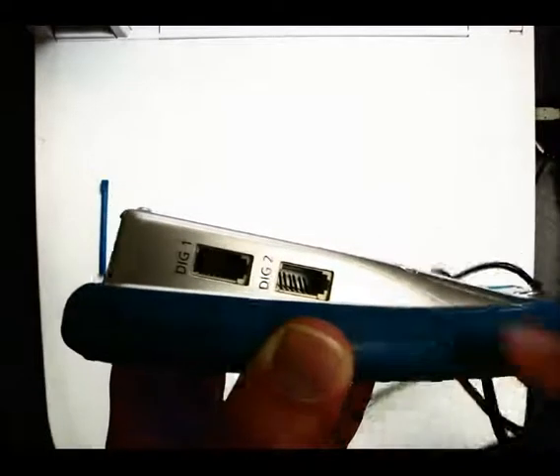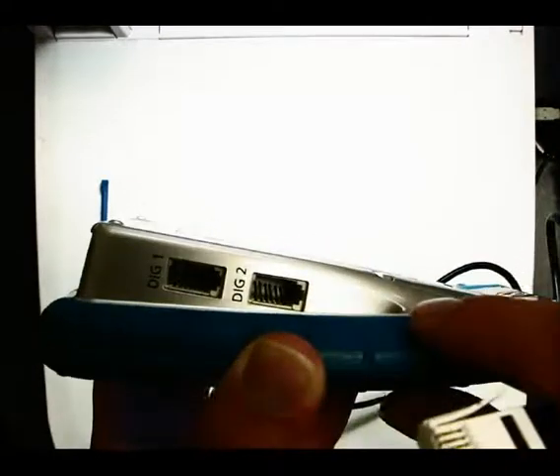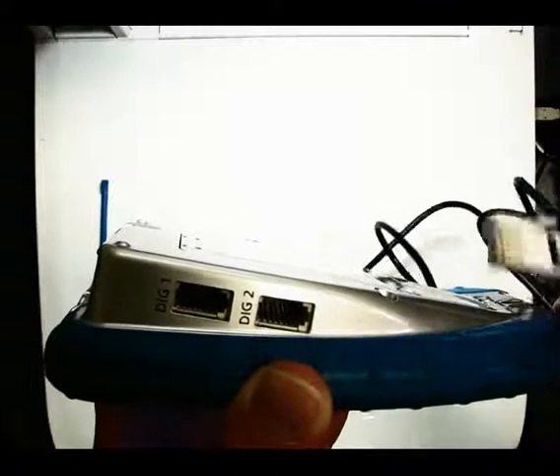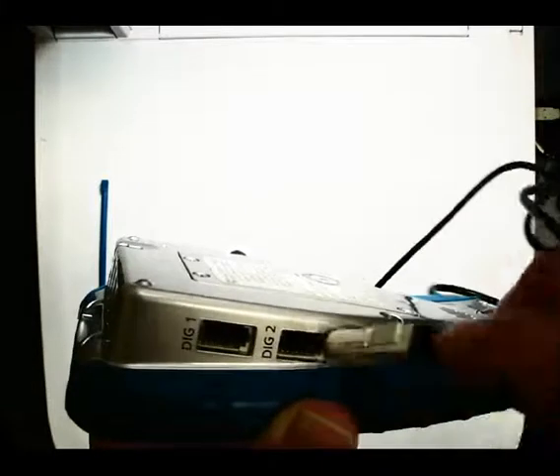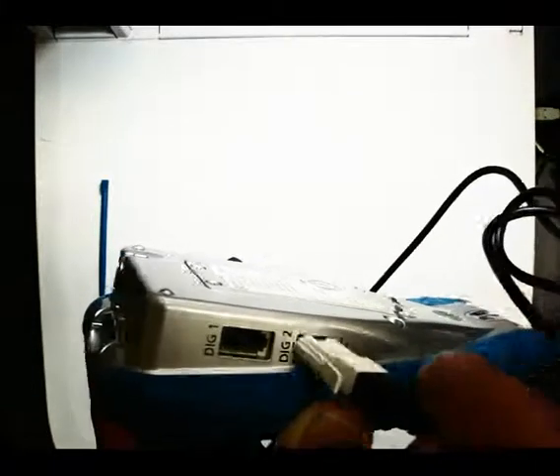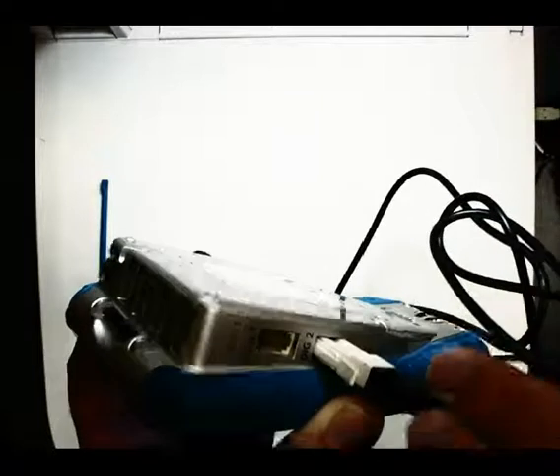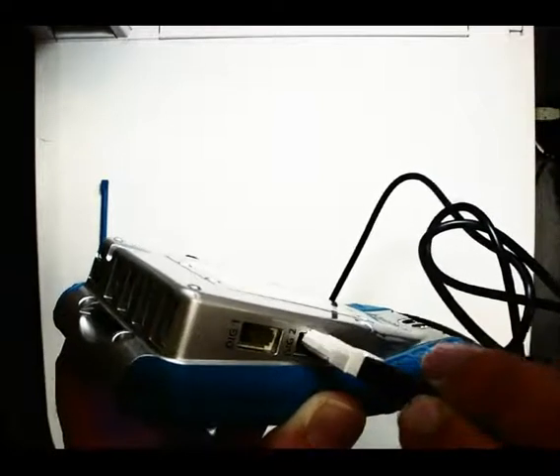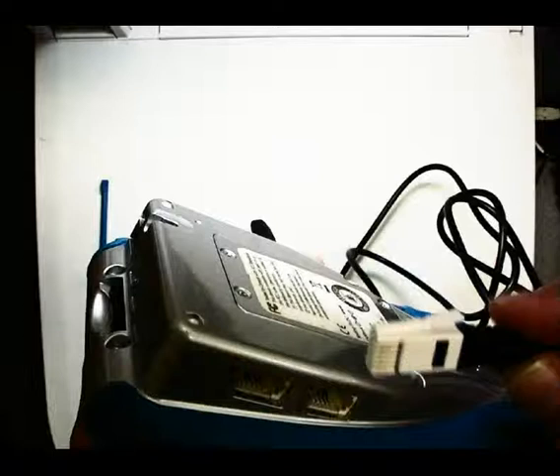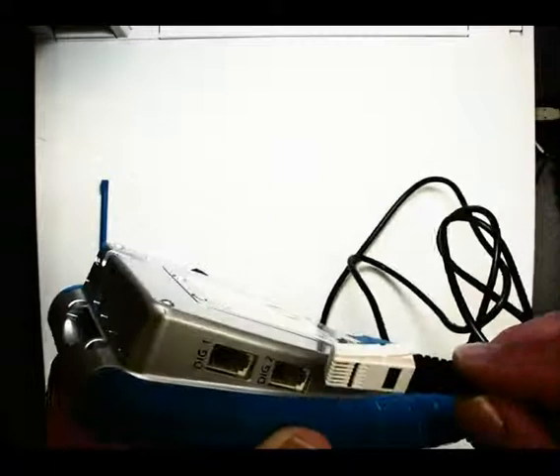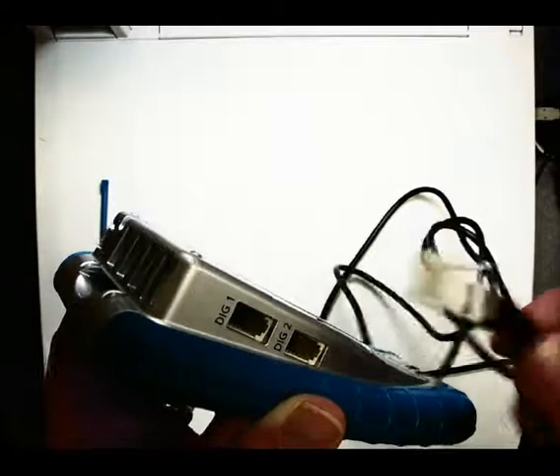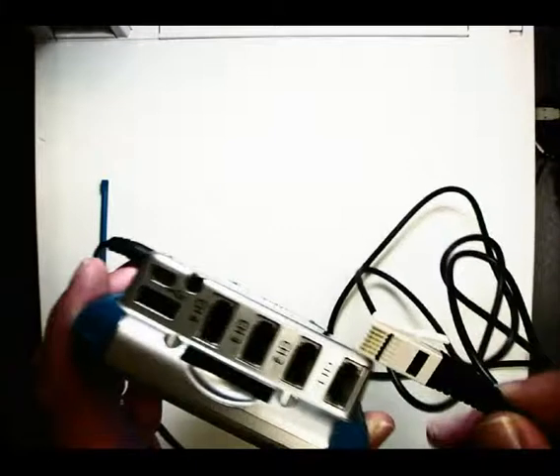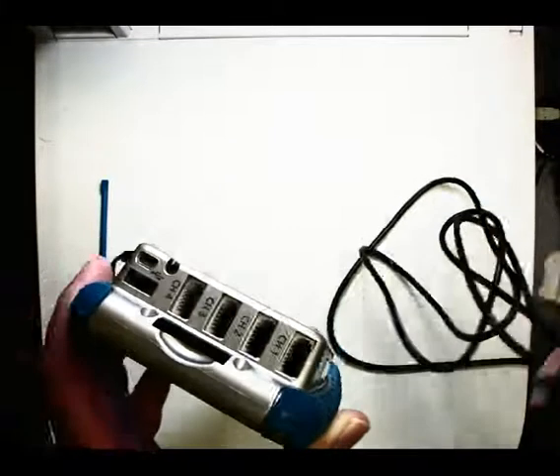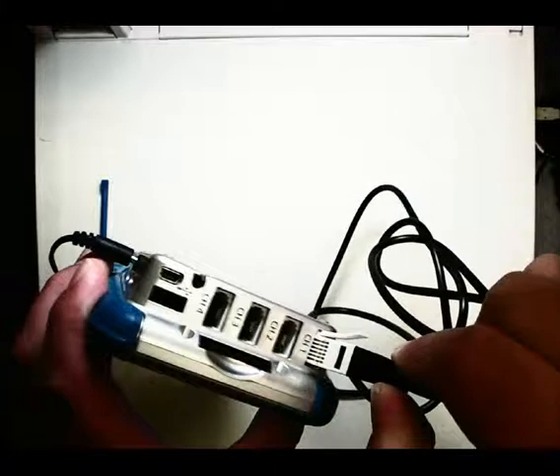You can see these little metal bars inside there. Here, if I were to try and match up the metal with the metal, it would have to go this way, but notice the plug doesn't fit in there. Now the real danger is that you could force it in there and make it work, except that would not be good for either the LabQuest or the probe. So you have to look at each sensor and decide whether it goes into the digital inputs on the side or the channels on the top. For this temperature probe, it plugs in right at the top, just like that.